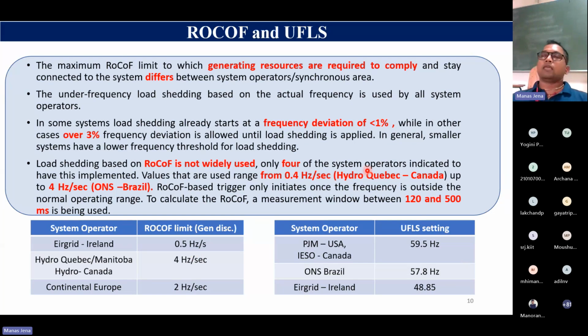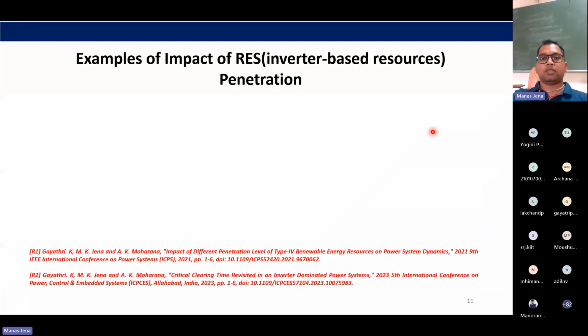So for the same contingency, if you have less inertia, you may unnecessarily trigger some of these UFLS protection schemes, and then what will happen? You will lose loads. In the 2019 blackout, if you go through the report, you will see that some of those loads were connected to the metro lines, and passengers were stuck. This is what we need to avoid, isn't it? So that is where inertia comes into the picture in a big way. A system with lower inertia will experience higher ROCOF, and that needs to be considered for the future power system. I'll also suggest some of the things which can be done.